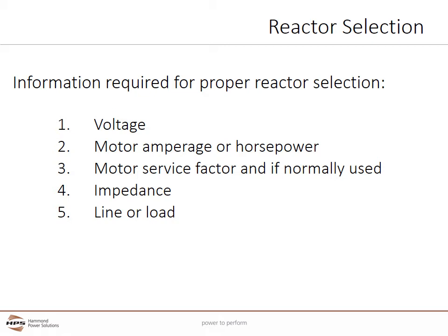Although in HPS's case, the Centurion reactors can be used interchangeably on either the line or load side. There may be other useful data points such as the VFD to motor lead length, the VFD's rated amperage, the motor type, and carrier frequency, but for the sake of basic training, we will cover these five parameters.